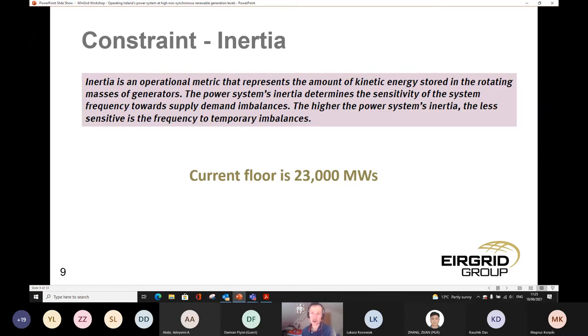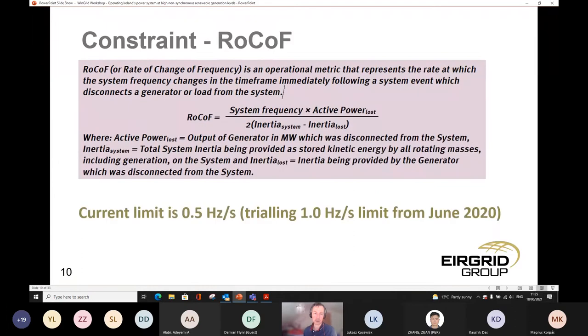Our system has a peak of about 6,000 megawatts, and our largest infeed is of the order of 500 megawatts, which could be an interconnector. The loss of a 500 megawatt infeed on a 6,000 megawatt system at peak is obviously quite a big shock to the system. So we need plenty of reserve and inertia on the system to manage the resulting frequency deviation and the rate of change of frequency, or RoCoF, that results from that.